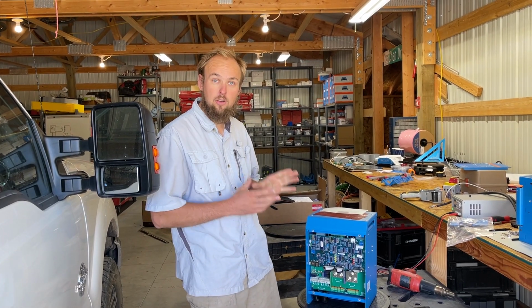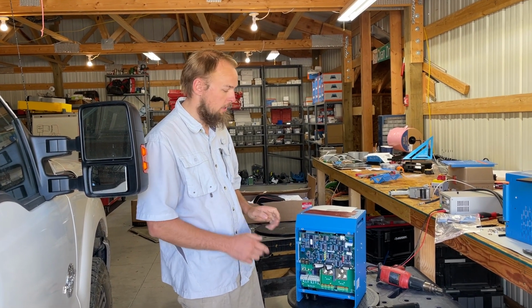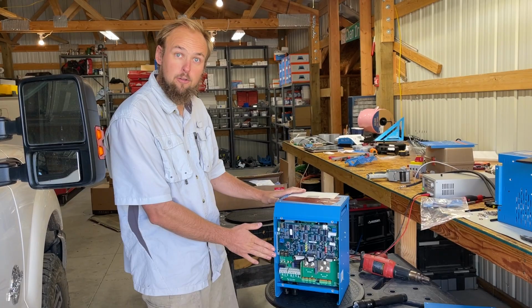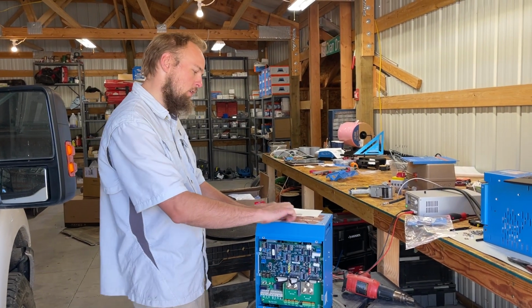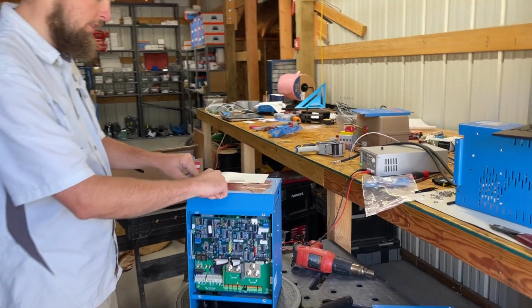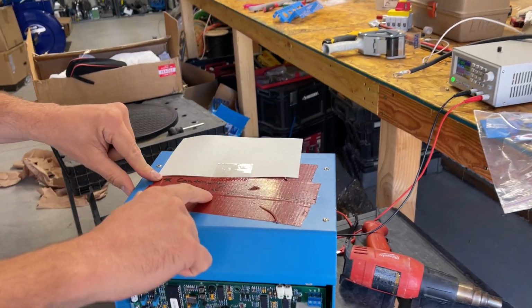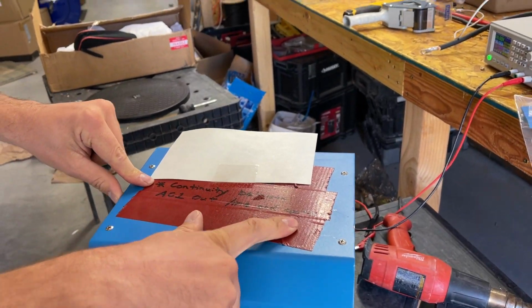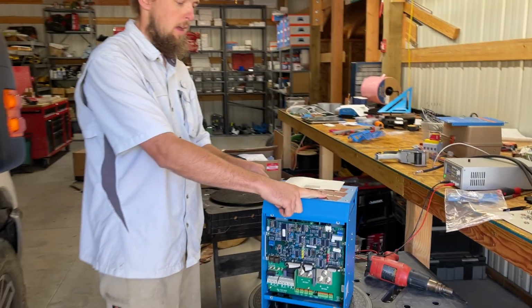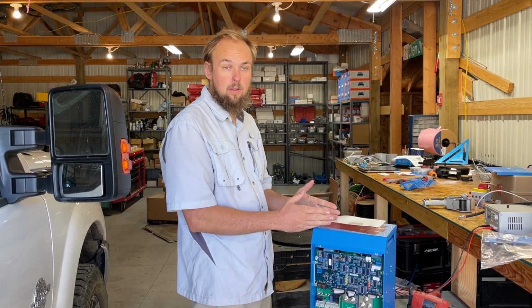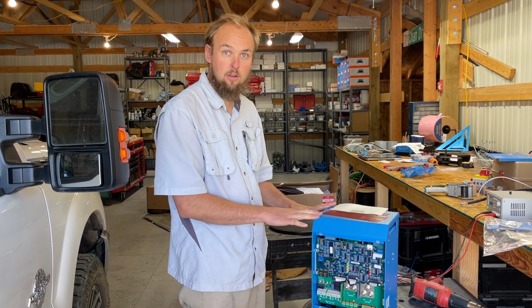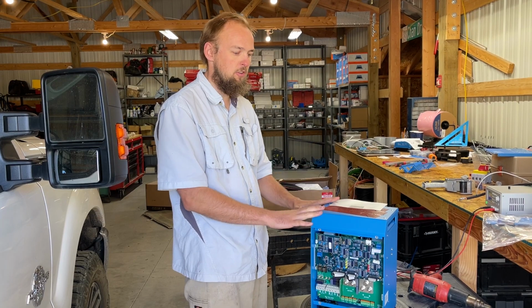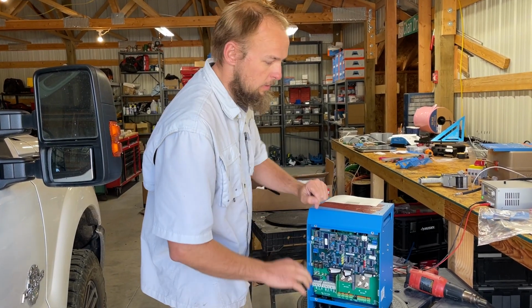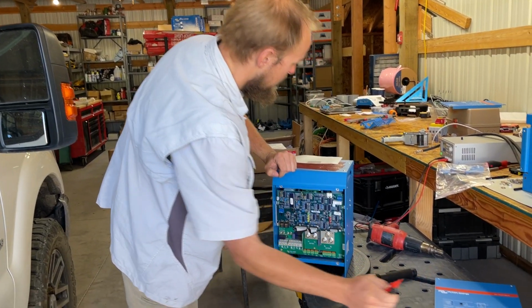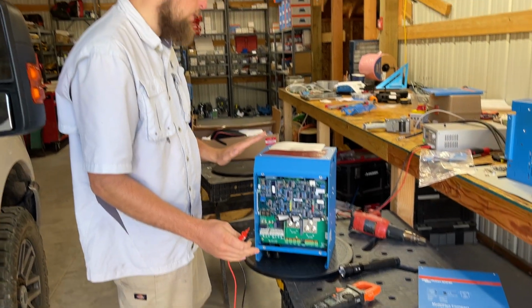I just thought I'd show you something we got here real quick. We just got this inverter in for repair, and it has a note on top of it that says there's continuity between AC1 out line and neutral. And the report that we got from the place that sent it to us had some little bit contradictory information. So we're trying to figure out what the fault is, but it's saying that it's a continuity problem.